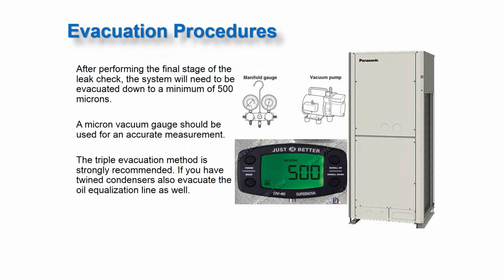Okay, and here we are talking about evacuation procedure. So we want to clean the inside of our refrigeration pipes. The way that we do that is we do an evacuation with our vacuum pump, and we have our digital gauges here to see where we're at in microns. So we pump the system down to 500 microns. This will ensure that we remove any moisture or debris inside of the piping system so that we have a clean piping system. Then we can charge up with refrigerant.